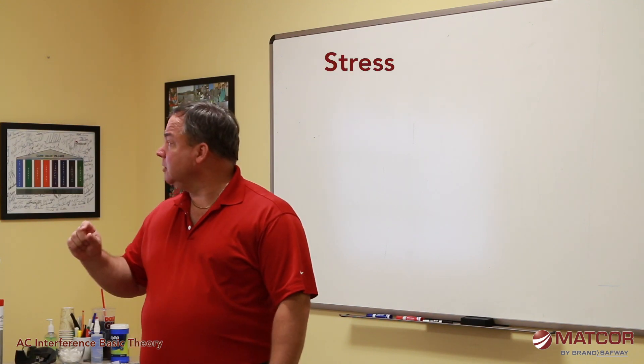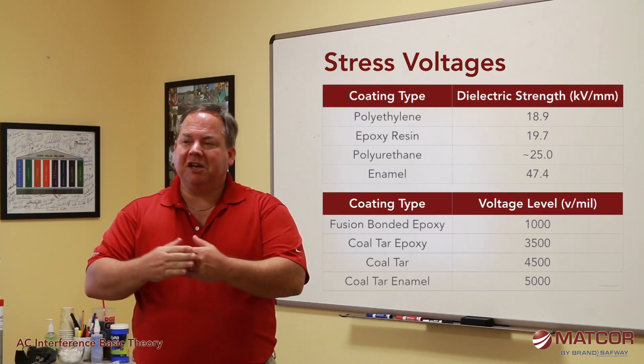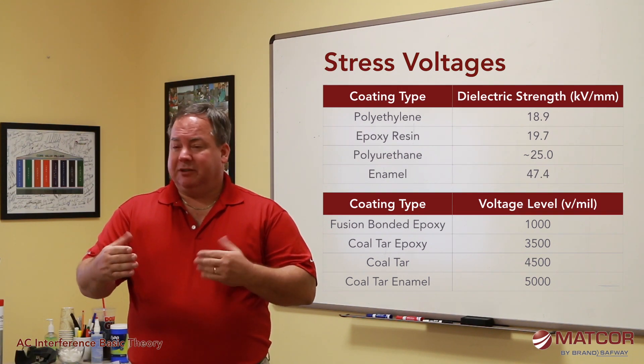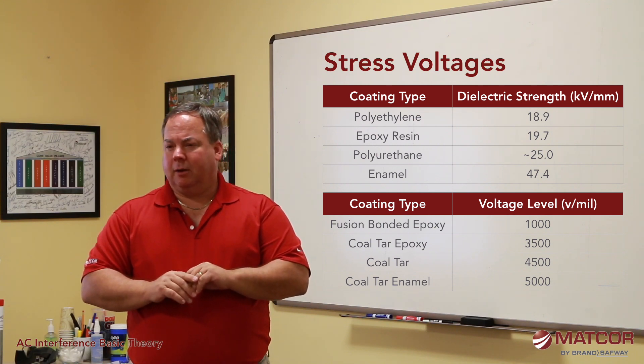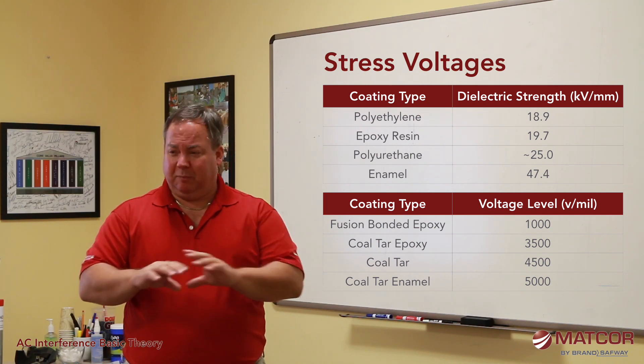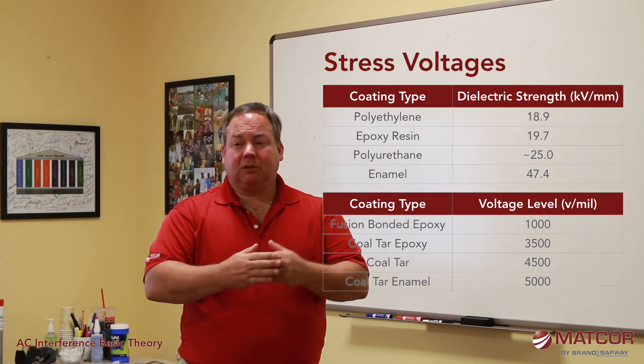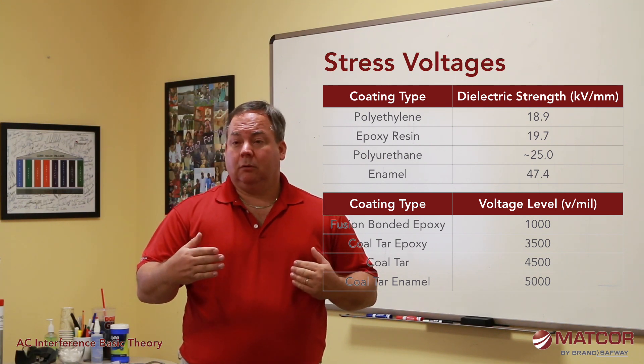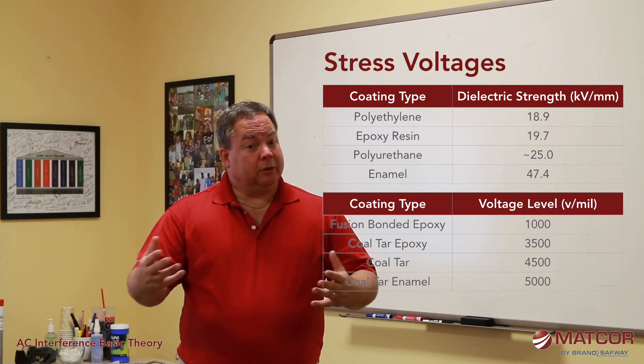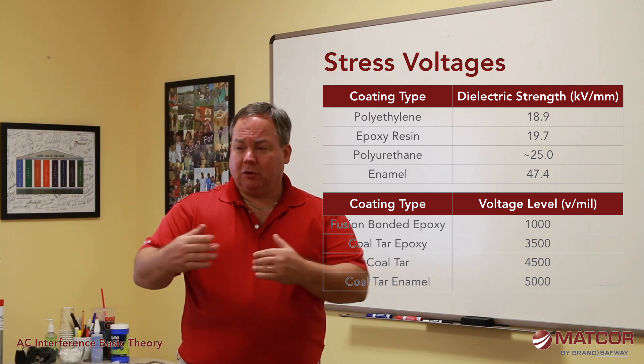Pipelines have coatings — most pipelines, almost all oil and gas type hydrocarbon pipelines, are going to have a coating system. That coating can handle only so much voltage stress. Different coatings have different amounts of voltage stress they can handle. If you exceed that voltage gradient, the coating can be damaged — it'll frizzle up, become weak, go friable. Bad things can happen to a coating system if it's subjected to a voltage gradient higher than what it's rated for.